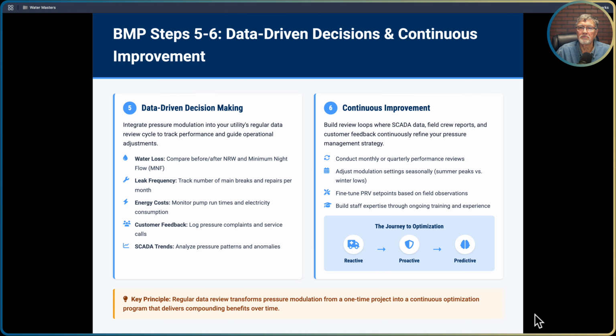And then lastly, continuous improvement. It's rarely going to go perfect the first time. So you want to build review loops where SCADA data, field crew reports, and customer feedback continuously refine your pressure management strategy. So we're really looking at the data. We're looking at those anomalies like we talked about in step 5, determining where they are and making the improvements to deal with them so everything flows smoothly, and then we can start rolling this out to other pressure zones. So you want to conduct monthly or quarterly performance reviews and adjust your modulation settings seasonally, for summer peaks and winter lows, and you're going to want to look at your usage patterns there.